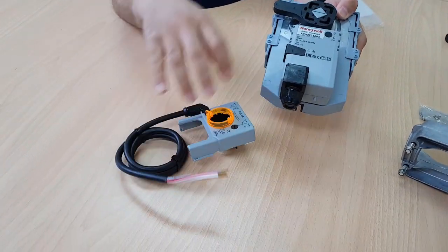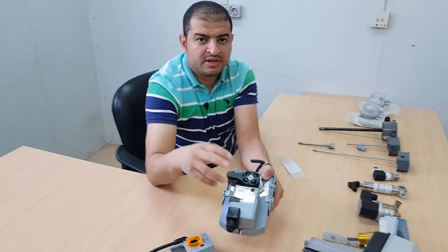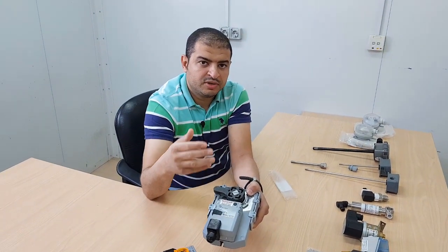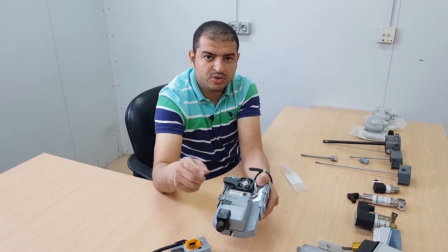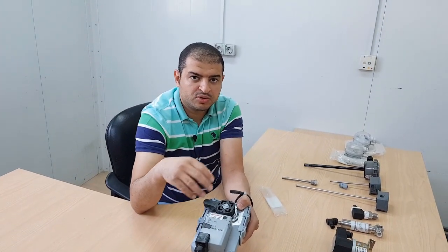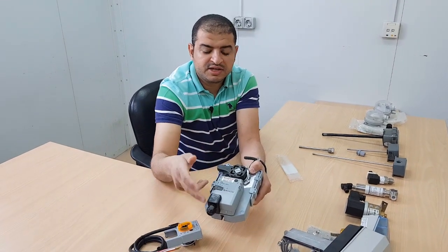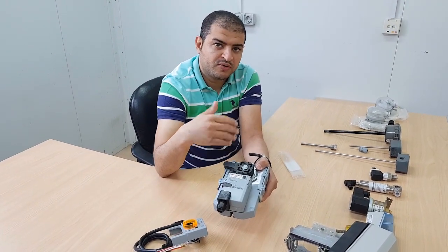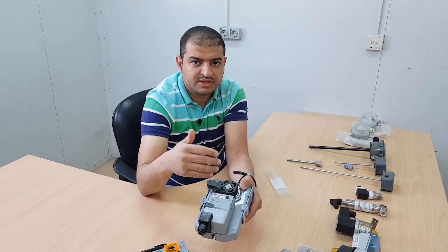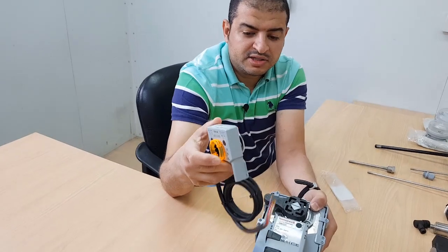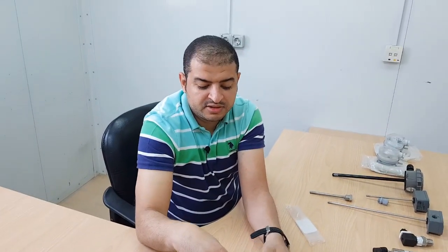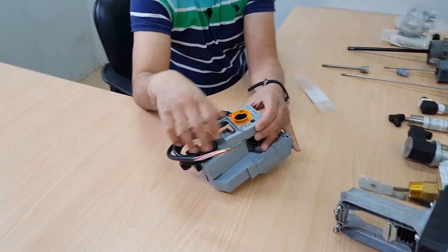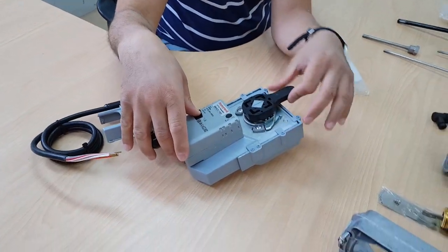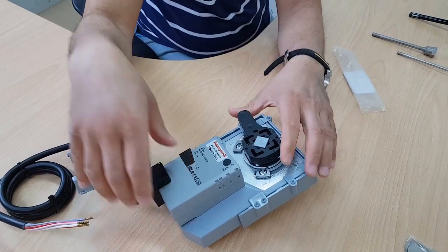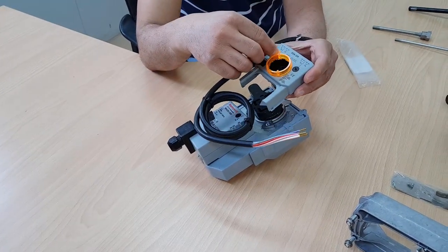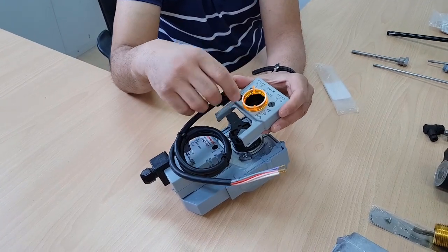Why? Because this one only gives on and off. I need to open and close, so I will send a signal to this actuator to switch on or off, or close or open the butterfly valve. But it doesn't give any feedback. So to convert it to a modulating type that sends feedback, I'm using this auxiliary contact, which is fixed above the actuator, and based on the rotation of the actuator, it gives me the status of the actuator's location.